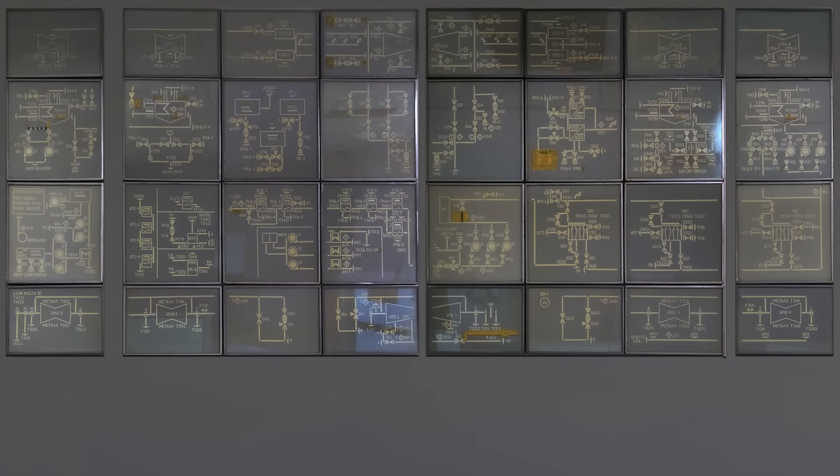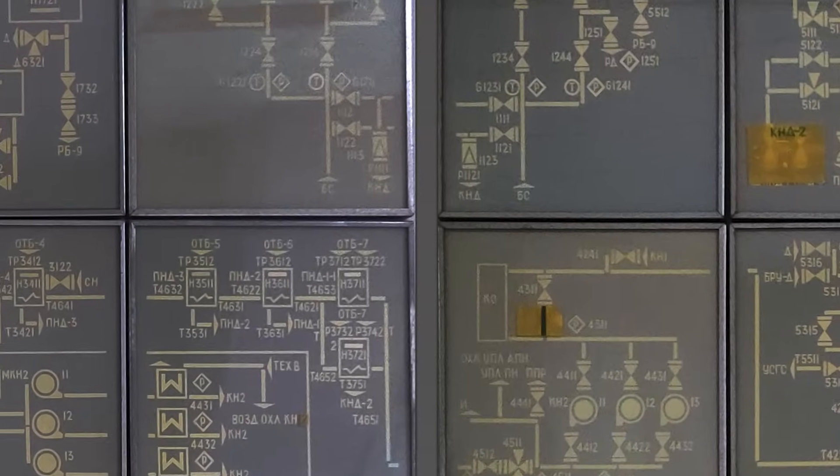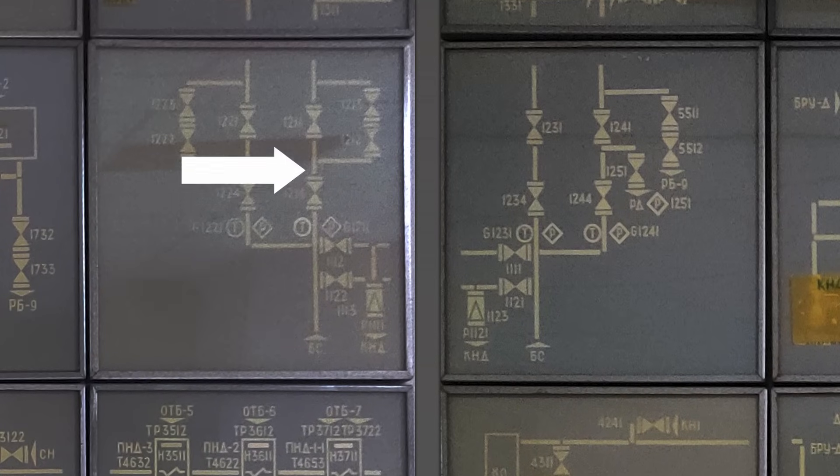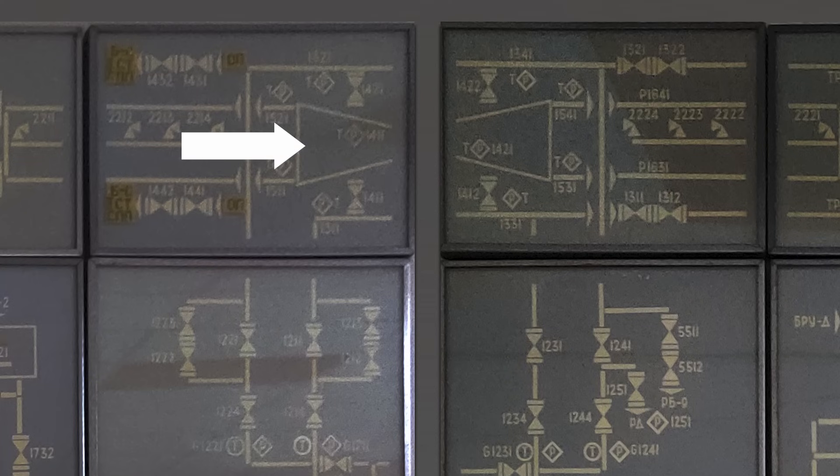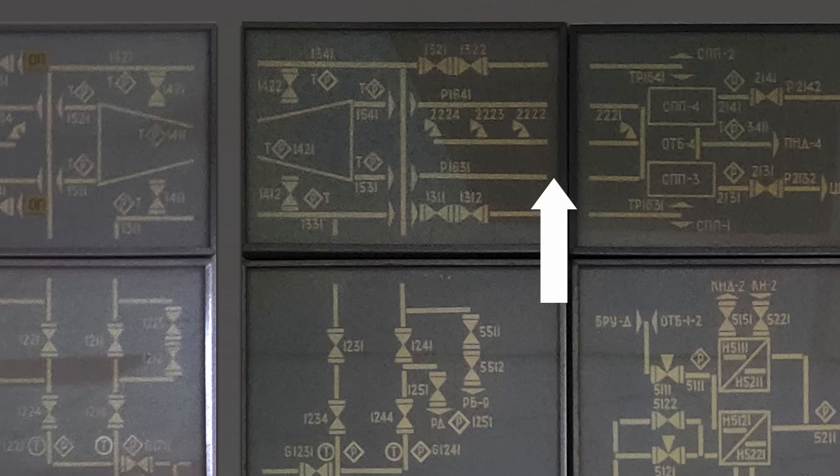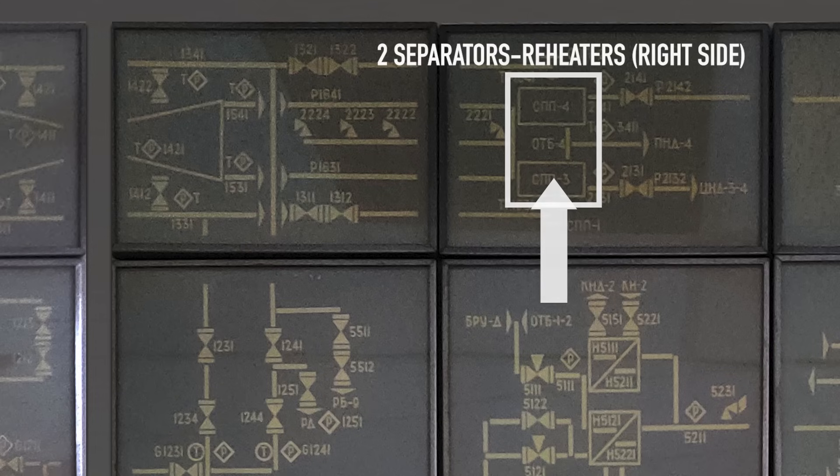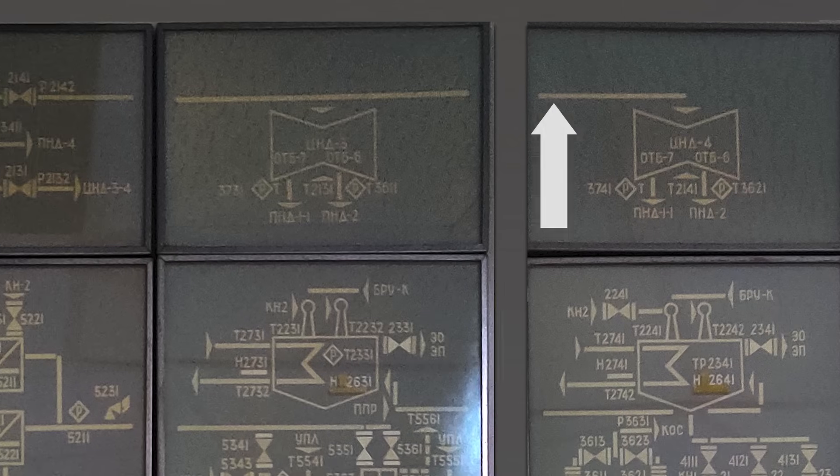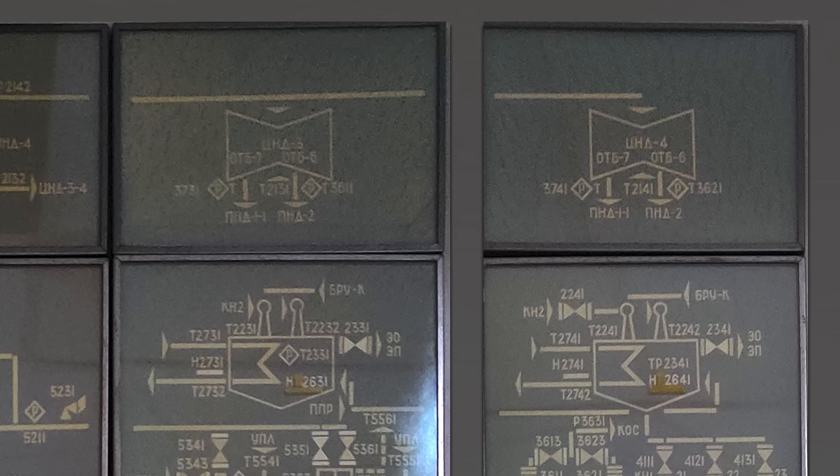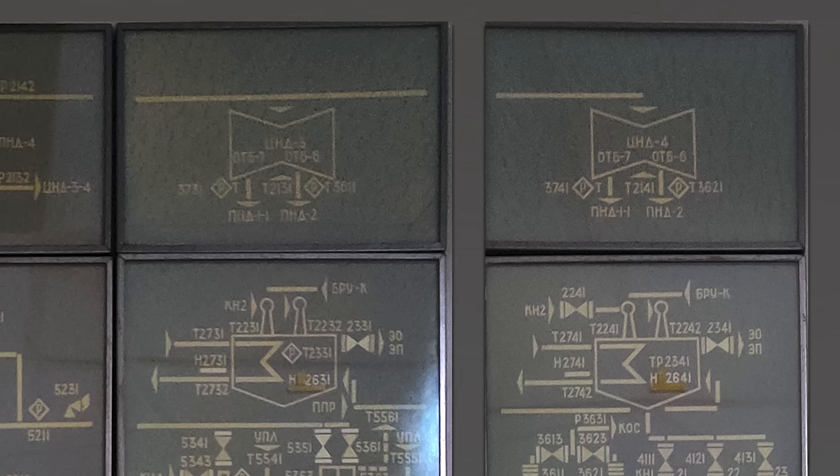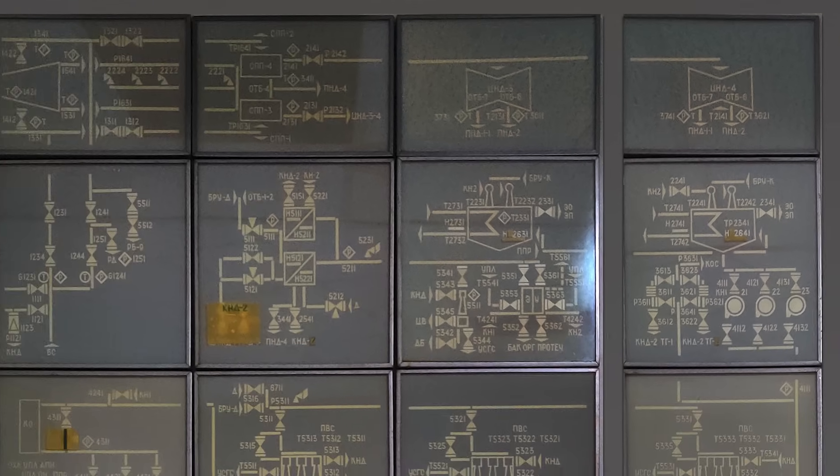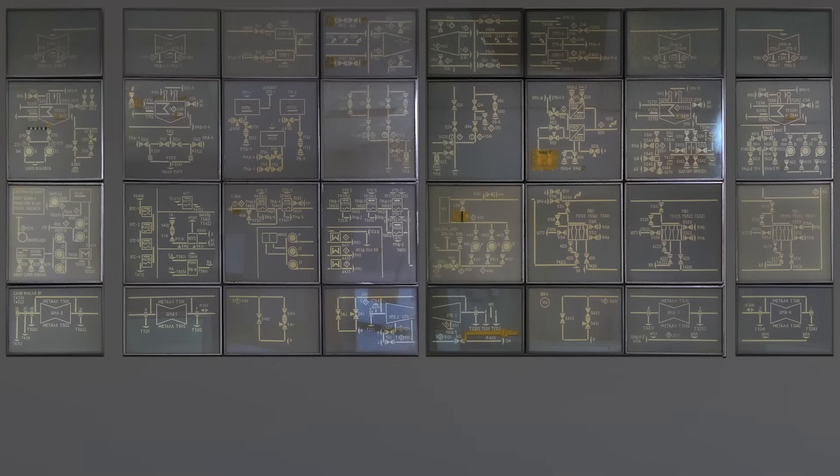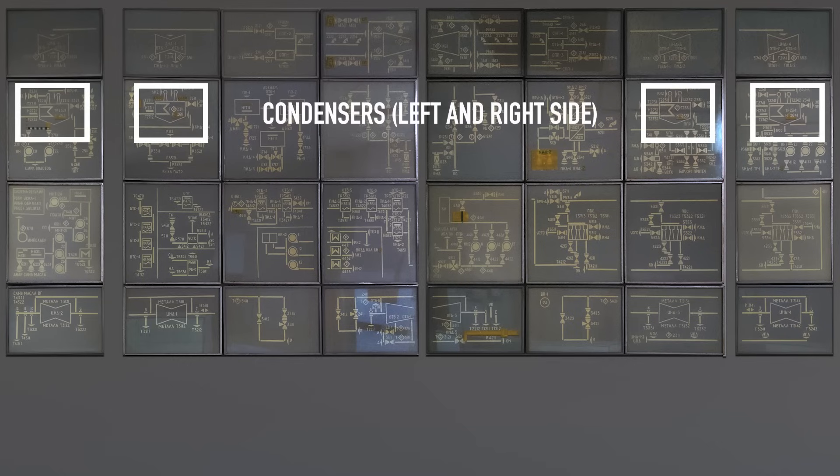So, high pressure steam from the drum separators enters at this place. Then it passes through stop and control valves before reaching the high pressure section. When its job is done there, the steam enters four intermediate steam separators and reheaters. There it gets superheated and any residual moisture is removed. Then it comes to four low pressure cylinders. So, basically the steam rotates turbine in all five cylinders, and this way its energy is used with higher efficiency. But by the time it exits them, it's already cooler and has lost energy. Now we need to return it back to reactor, but first we have to turn it back into liquid water, and here come these four condensers.